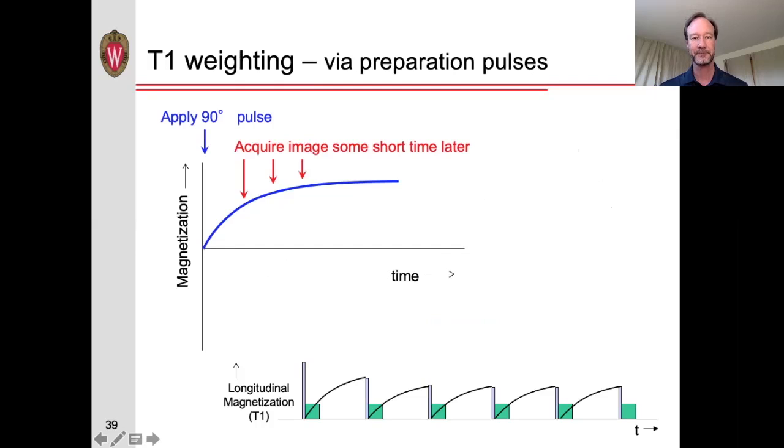So for example, in this case, this is what we call saturation recovery. We could use this for some T1 weighting. That is, if we apply a 90-degree pulse, wait a certain period of time, and then remove the remaining transverse magnetization, and then acquire our data, what happens is that the signals will not have fully recovered, depending on where they'll recover, depending on the T1s.